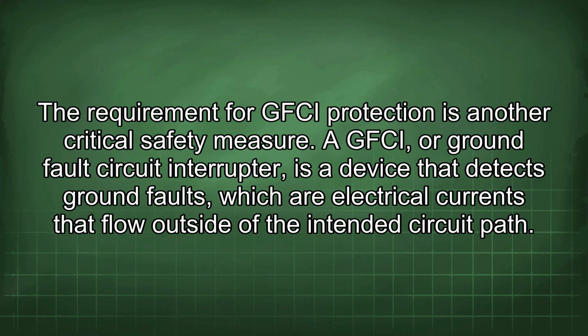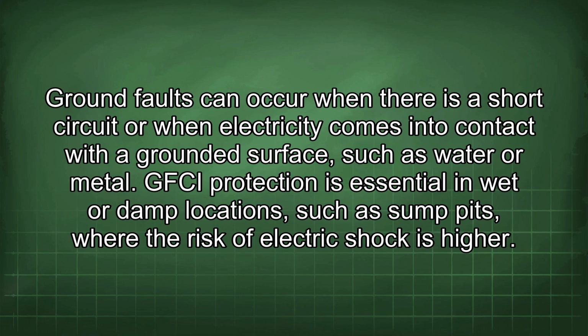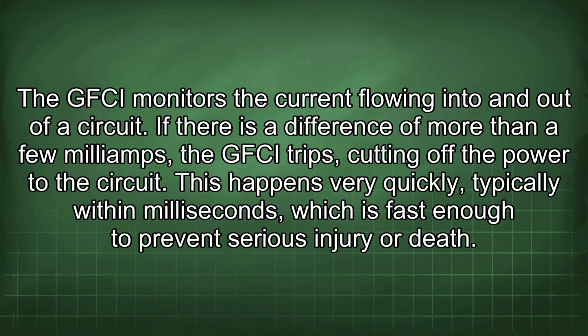A GFCI, or ground fault circuit interrupter, is a device that detects ground faults, which are electrical currents that flow outside of the intended circuit path. Ground faults can occur when there is a short circuit or when electricity comes into contact with a grounded surface, such as water or metal. GFCI protection is essential in wet or damp locations, such as sump pits, where the risk of electric shock is higher. The GFCI monitors the current flowing into and out of a circuit.